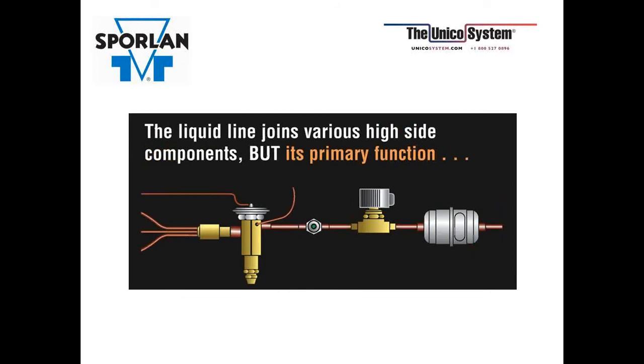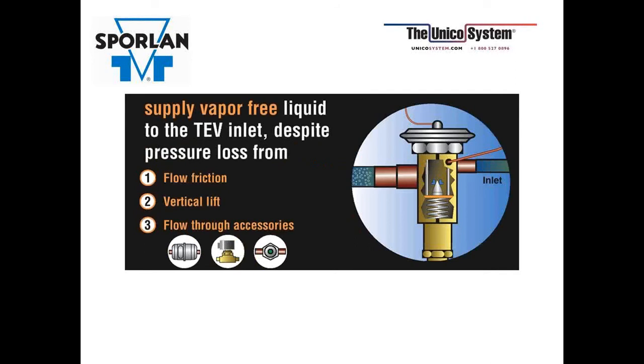The liquid line joins the various high-side components, but its primary function is to supply a vapor-free liquid to the TEV inlet. And by vapor-free liquid, we mean subcooled liquid. Vapor formation in the liquid line is a progressive thing. When the first few bubbles occur, they offer added resistance and an added pressure drop, which creates more vapor, which then creates more pressure drop. So vapor increases the pressure drop through the accessories, making it even harder to estimate how much total pressure drop you're losing. Pressure drop due to flow friction can be minimized with proper line sizing and design.